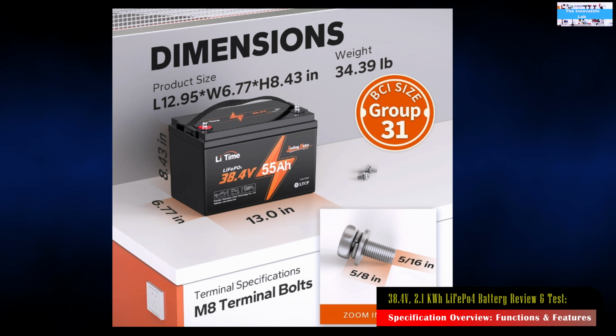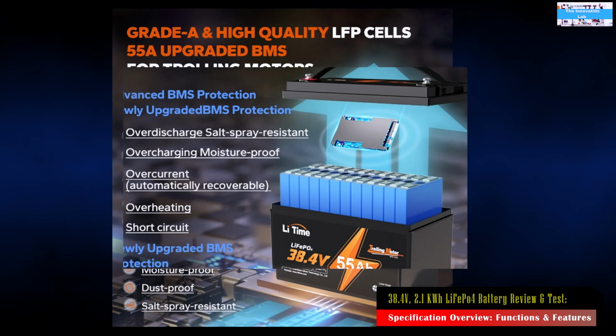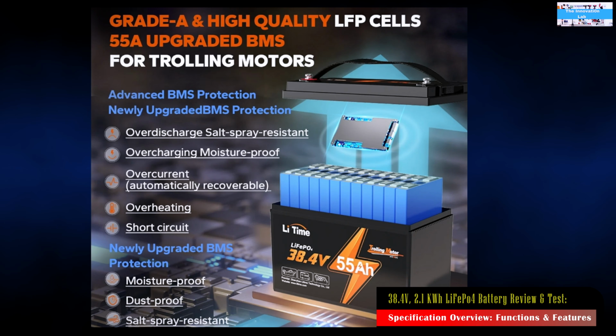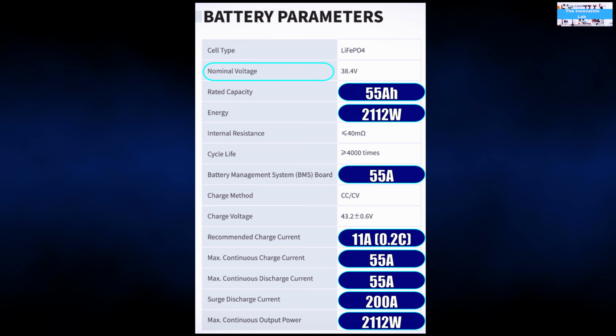As we've already talked about, this is a lithium phosphate battery chemistry, and all the cell types inside the battery are lithium phosphate. The battery has a nominal voltage of 38.4 volts, a rated capacity of 55 ampere hours, and it can store up to 2.1 kilowatt hours of energy.